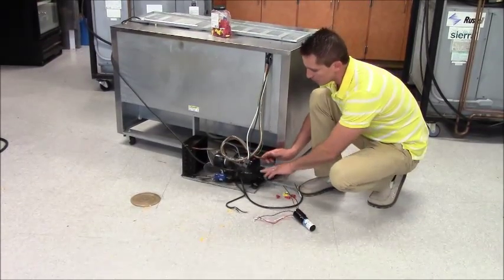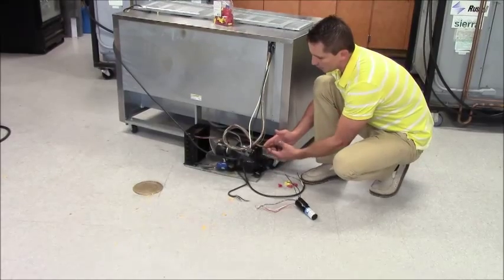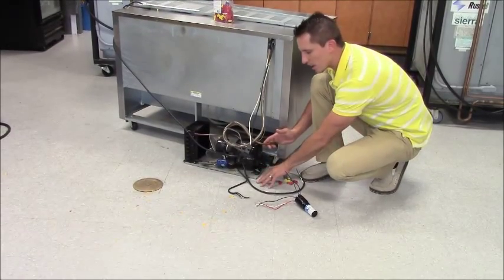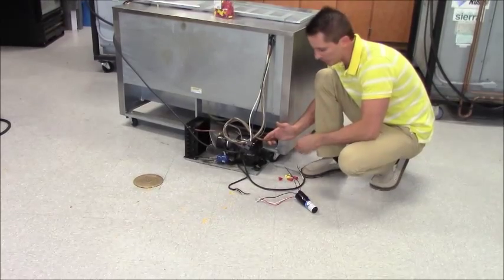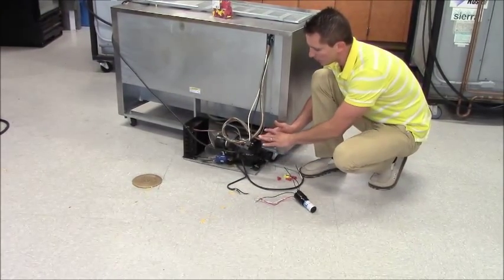Usually what happens is your start components go bad. So what we've done today is we've removed the compressor and put it on the ground, so you guys can get a very good visual on how to hook this 3-in-1 hard start kit up to your compressor.